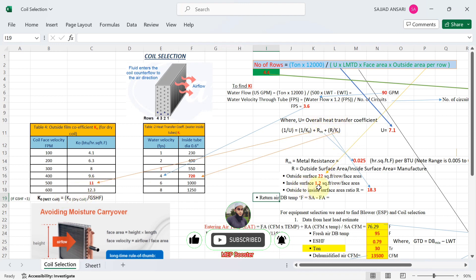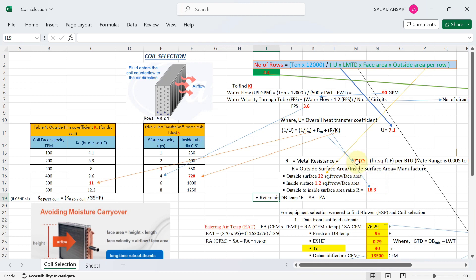Remember: k₀ is 11, metal resistance Rm is 0.025 from the manufacturer catalog, capital R (outside to inside surface area) is 18.3. For ki — the inside heat transfer coefficient — you get this from Table 2. To use Table 2, you first need to calculate the water velocity inside the tube.